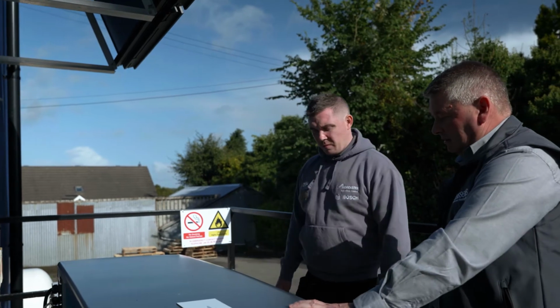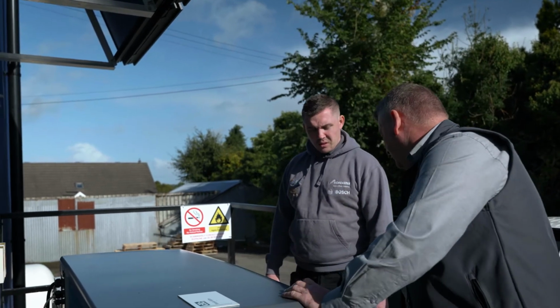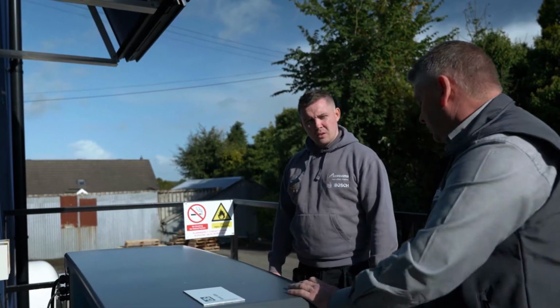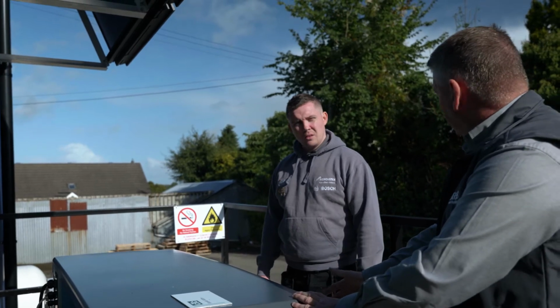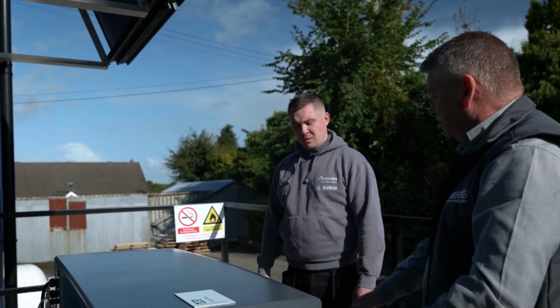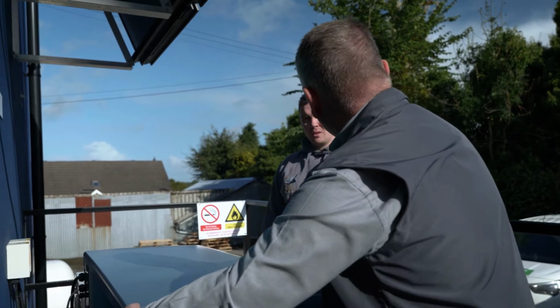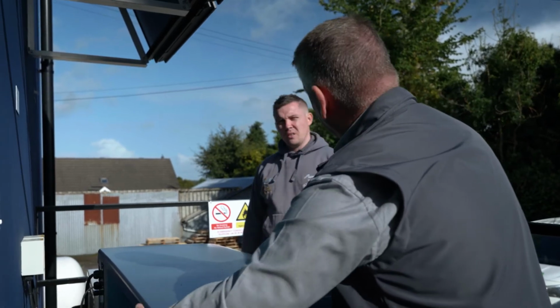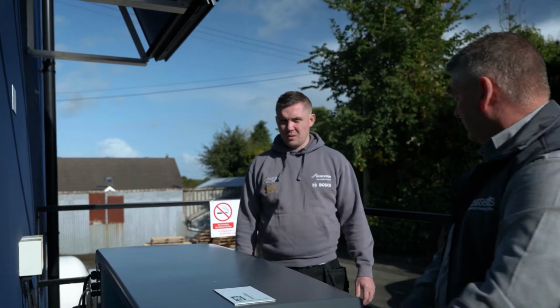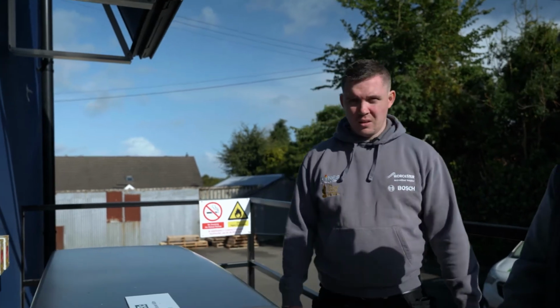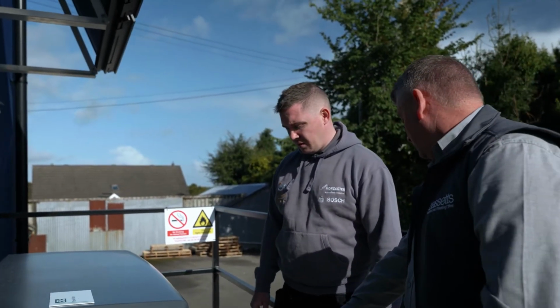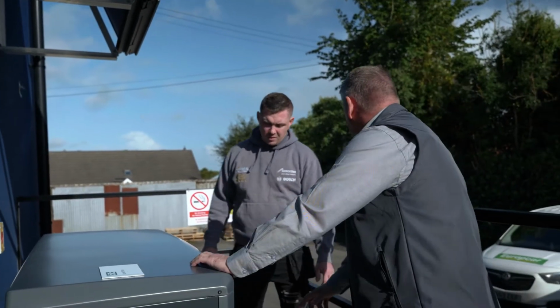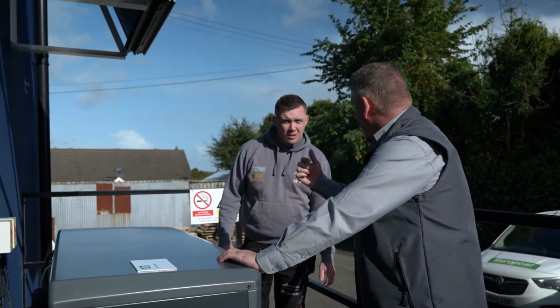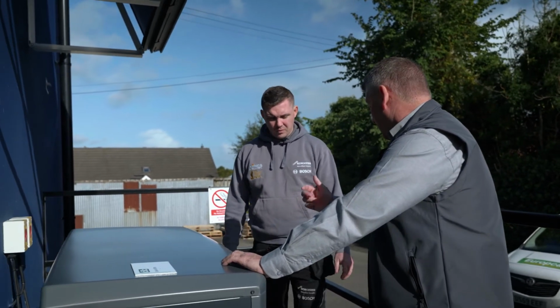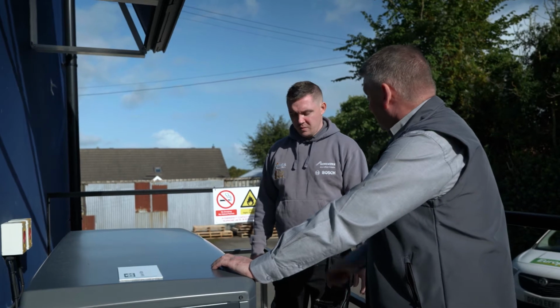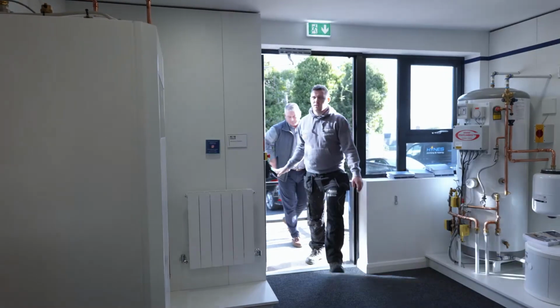Very little maintenance. You just check no leaves or debris is caught in the fan. You don't push any obstacles up in front of the fan so as you prevent air circulation, and that nothing has damaged the fans. They restrict the air current going through the evaporator. There's a drain at the bottom for your defrost. It's an automatic defrost mode, you don't have to do anything, and there's an inbuilt frost-stat that works at 3 degrees on it.